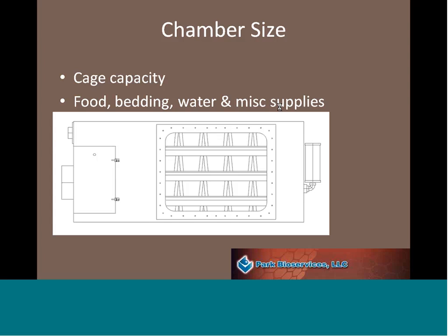Where that really becomes important is that the area where you're going to have potential failure of a project is having too many entries and too many exits of materials. So if the isolator is large enough to load up with all of the supplies for the entire duration of the study, that would be ideal. That might be impractical. At some point in time, you're going to have to take out waste materials, or take out any animals that have died. You're going to have to add in more supplies, but you really have to maximize and get as many supplies in as you can at one time, just to minimize the number of entries and exits.